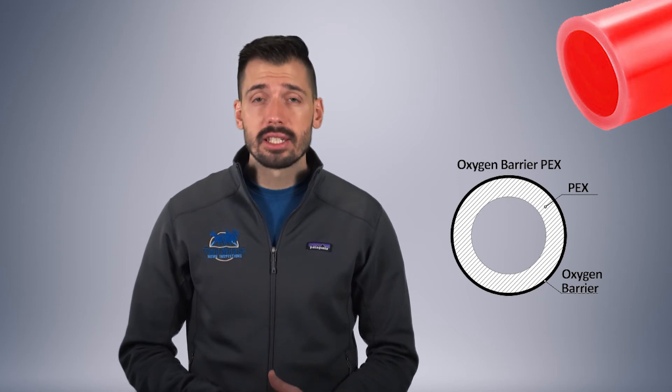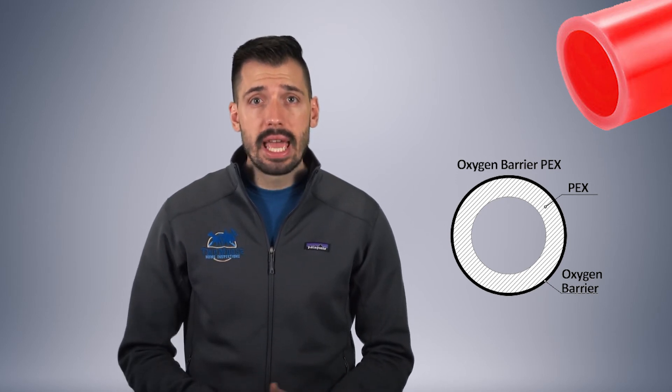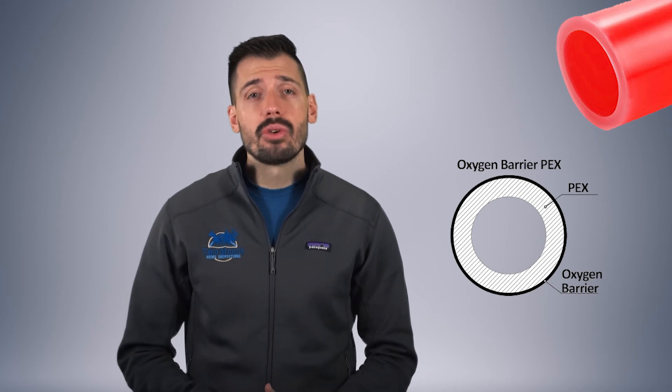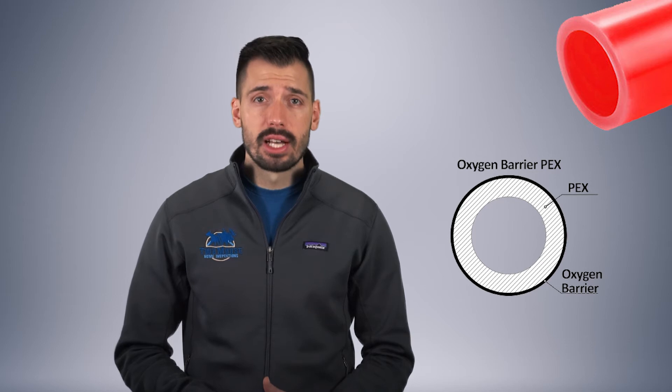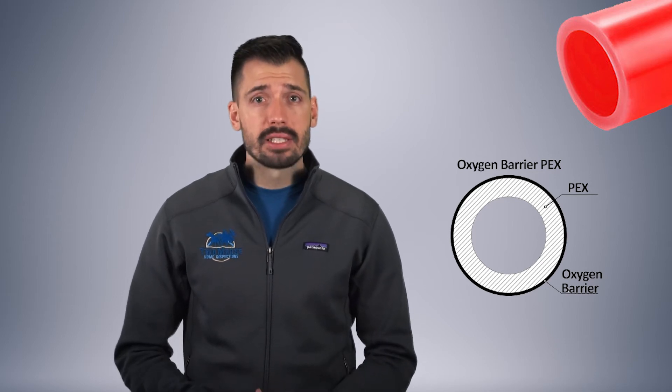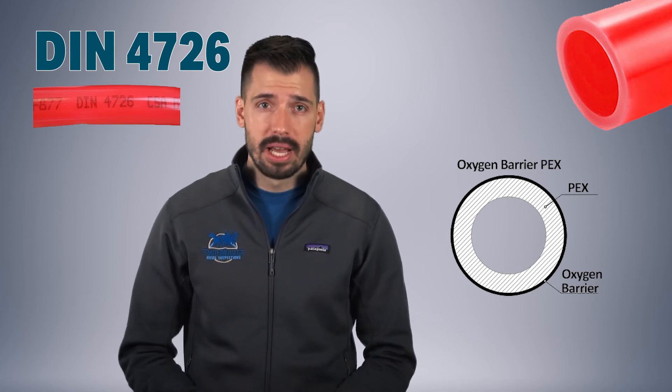Oxygen barrier PEX is primarily used for hot water hydronic heating such as baseboard radiator heating, fan coils, radiant floor heating, and snow melting applications, which are known as closed-loop systems. These pipes can often be identified by their glossy surface. If a PEX pipe has an oxygen barrier, it may also have DIN 4726 printed on the pipe.